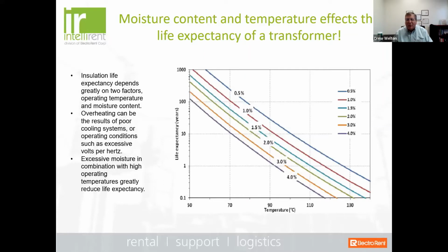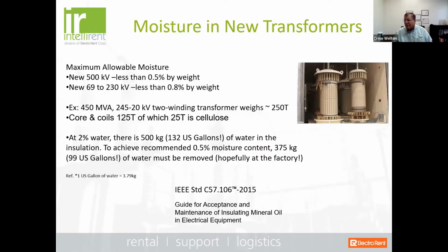And typically at this point, a lot of utilities will run their transformers pedal to the metal. You know, we're at full rating in terms of the load. And the higher the load, the higher the operating temperature. Overheating can be a result of poor cooling systems, or even operating conditions such as volts per hertz that we see sometimes close to generating facilities on GSUs. Excessive moisture in combination with the operating temperature greatly reduces the life expectancy. And you can see here on this graph, this is your percentage of moisture in the insulation, and this is your operating temperature. So combined, we're talking about serious conditions.